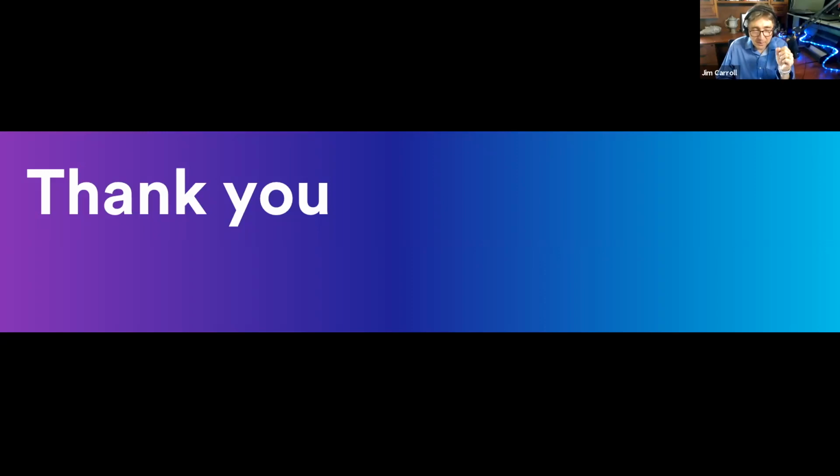Excellent. Here's a related question, an interesting one as well, and that's vibration. Have you done vibration tests? I suppose this would be in remote data centers or things in motion. Yeah, we have done the Telcordia testing on these, including vibration testing, and no concerns to date. I think it's GR-1435. We fully completed all the environmental testing, including vibration testing, and it performs well.